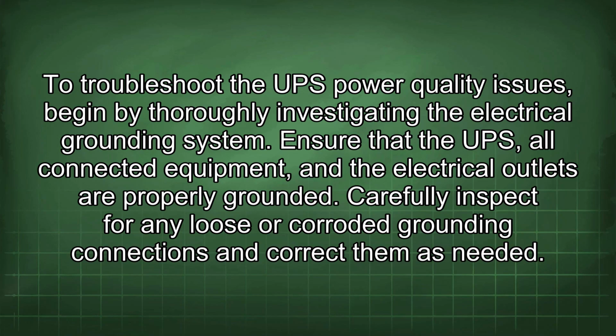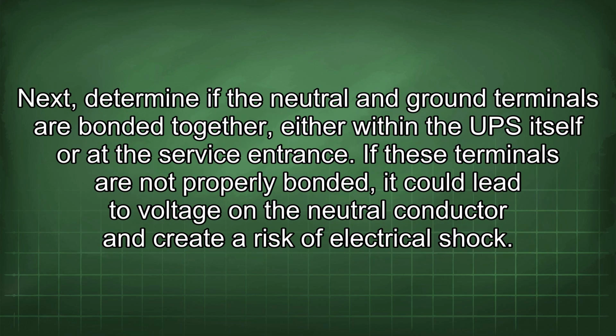To troubleshoot the UPS power quality issues, begin by thoroughly investigating the electrical grounding system. Ensure that the UPS, all connected equipment, and the electrical outlets are properly grounded. Carefully inspect for any loose or corroded grounding connections and correct them as needed.